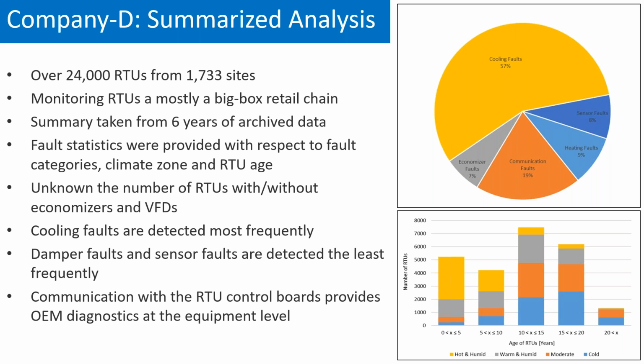This company is also able to communicate with the RTU control board, which is able to provide a level of fidelity at the equipment level that working at the BMS level or a retro controller architecture is not. They are able to directly pull fault codes from the OEM equipment and pull out more accurate and more pointed error codes associated with the RTUs.